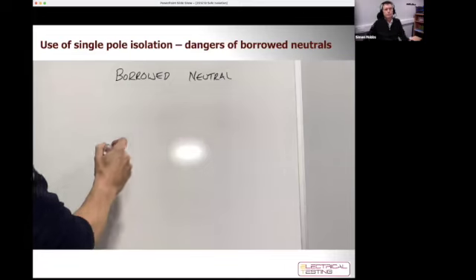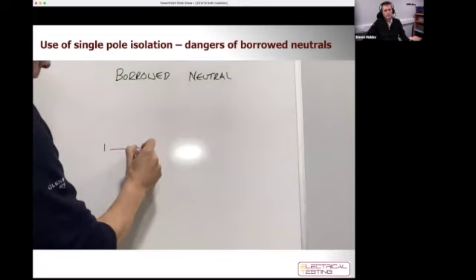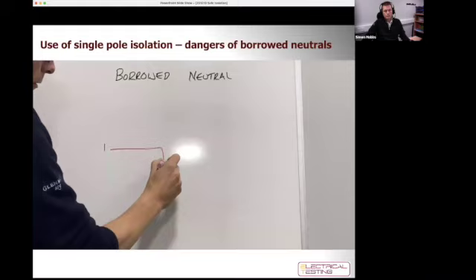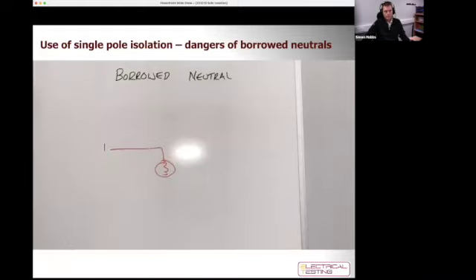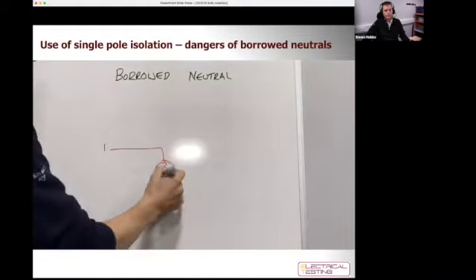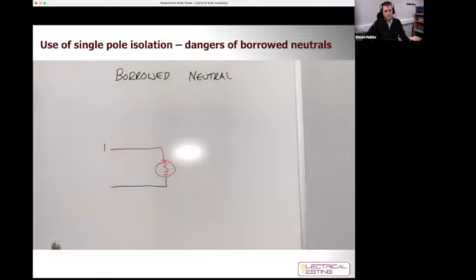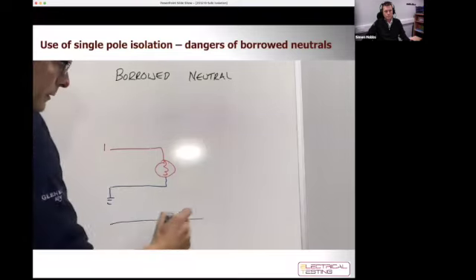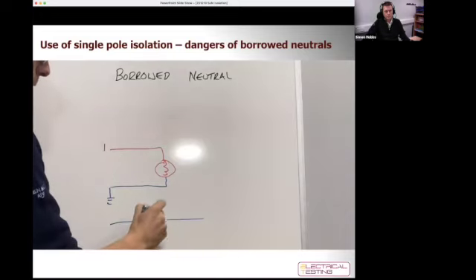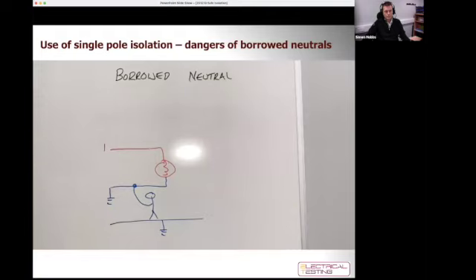So we're here to look at the subject of borrowed neutrals. If I draw circuit 1 and it comes down to a lamp on the line conductor, and we've got a neutral that's returning like so, and this is traditionally and commonly at earth potential. What that means is that if I am standing on the ground and I touch the neutral conductor on that circuit, I won't get an electric shock as it's at earth potential.